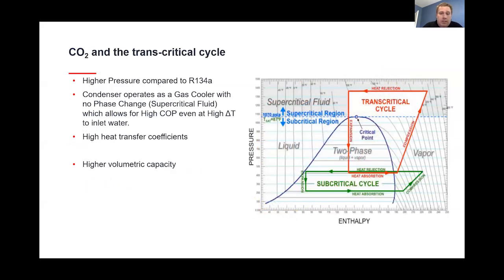So how do we produce these 176 degree water temperatures? It's really all because of the CO2 refrigerant. And the CO2 refrigerant is considerably higher pressure than R134A, but it's fully contained in an outdoor unit, which is fully outside of your building. And as you can see here, when you compare CO2 to R134A, it's at a higher pressure. When CO2 is rejecting heat to the water, we're in the transcritical cycle, and the CO2 is in the supercritical fluid state, which allows us to produce hot water all the way down to negative 35.